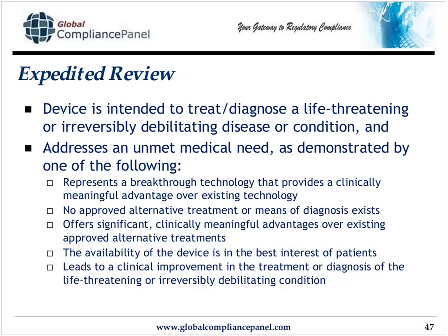An expedited review is a review that the agency performs when a device is intended to treat or diagnose a life-threatening or horrible disease or condition and addresses an unmet medical need. Not one of these. If you have a device that is intended to treat or diagnose a life-threatening condition, but the need is already met, you cannot get expedited review.